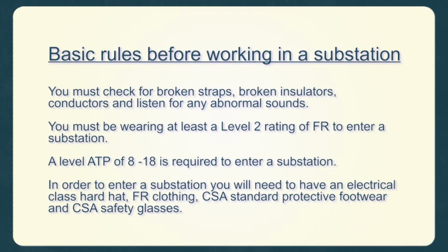Basic rules before working in a substation. You must check for broken straps, broken insulators, conductors, and listen for any abnormal sounds. You must be wearing at least a Level 2 rating of FR to enter a substation. A level ATP of 8-18 is required to enter a substation. In order to enter a substation, you will need to have an electrical class hard hat, FR clothing, CSA standard protective footwear, and CSA safety glasses.